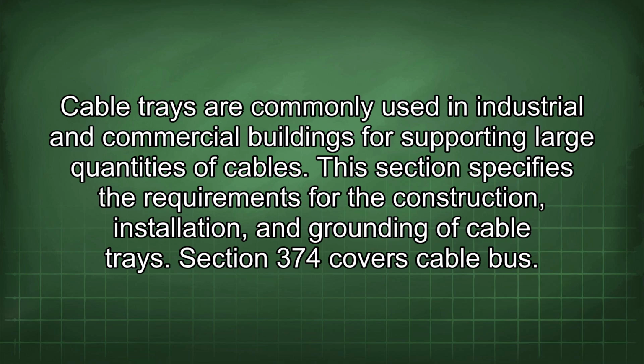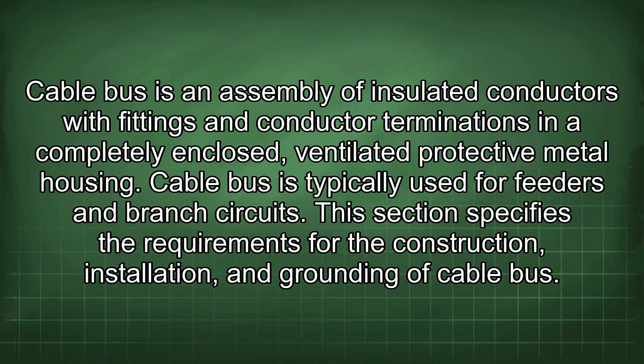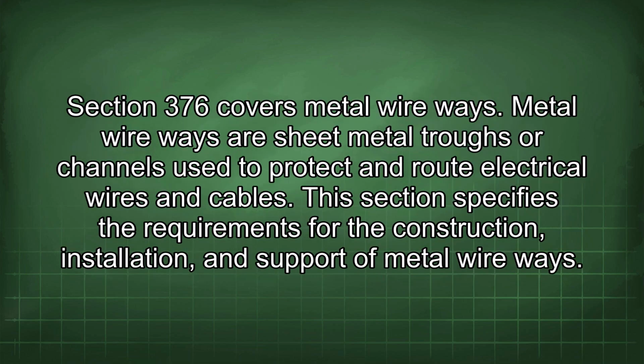Section 374 covers cable bus. Cable bus is an assembly of insulated conductors with fittings and conductor terminations in a completely enclosed, ventilated, protective metal housing. Cable bus is typically used for feeders and branch circuits. This section specifies the requirements for the construction, installation, and grounding of cable bus. Section 376 covers metal wireways. Metal wireways are sheet metal troughs or channels used to protect and route electrical wires and cables. This section specifies the requirements for the construction, installation, and support of metal wireways.